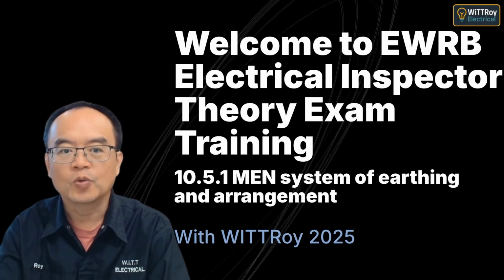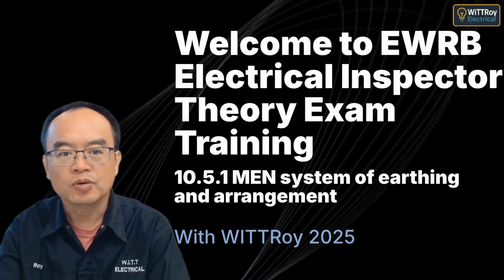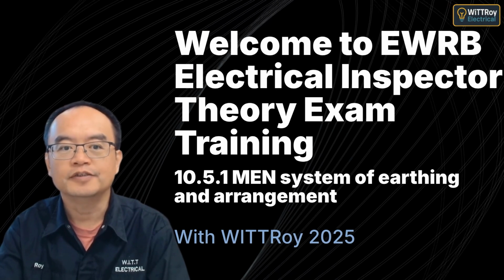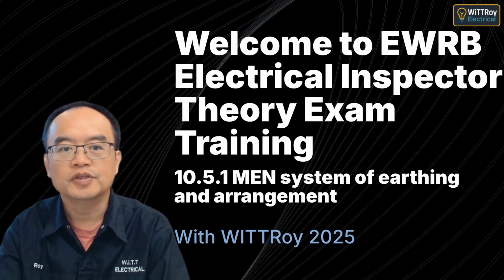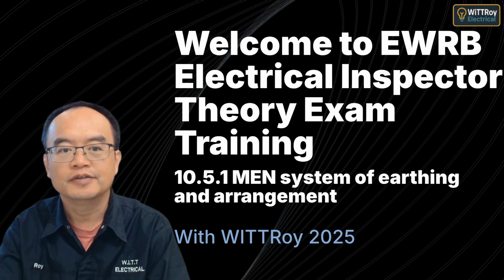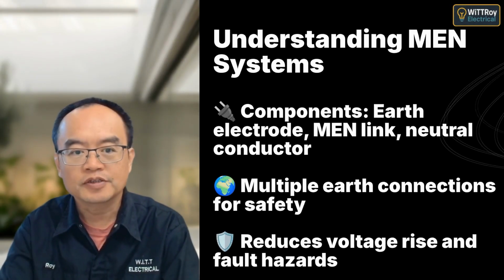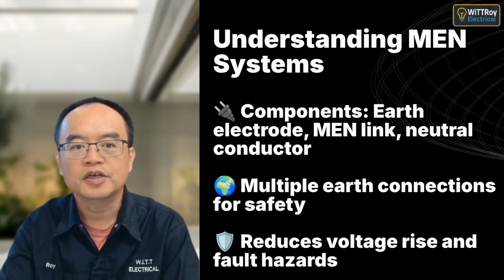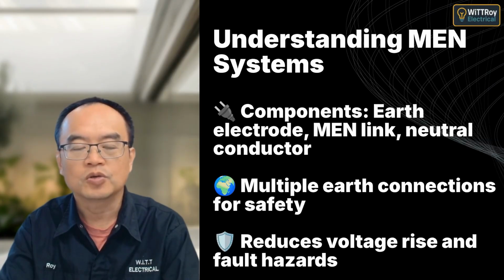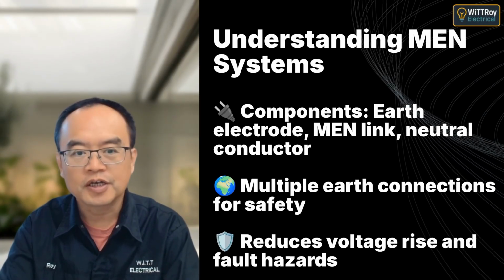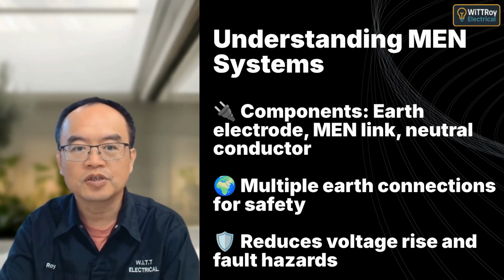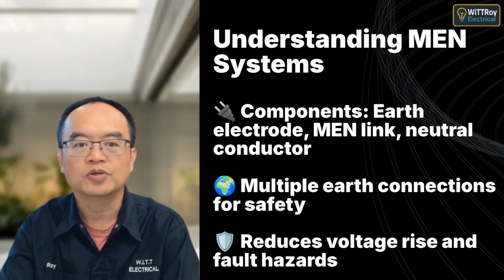Hi everyone, I'm Whit Roy. Today we're diving into the Multiple Earth Neutral (MEN) system. We'll cover its components, reasons for its use, and safety implications. The MEN system includes vital components such as earth electrodes, the MEN link, and neutral conductors. Multiple earth connections ensure safety by limiting voltage rise during faults and significantly reducing shock hazards.